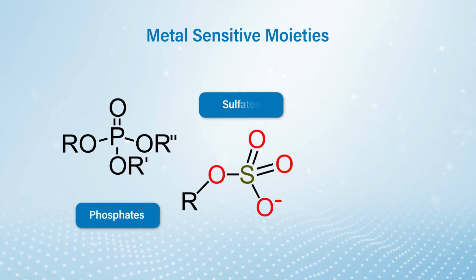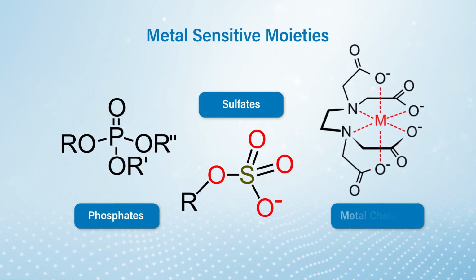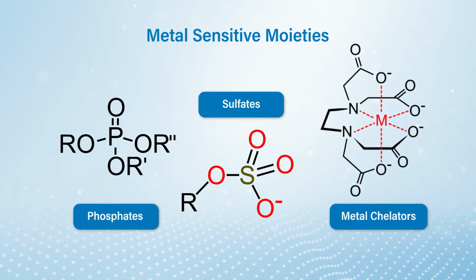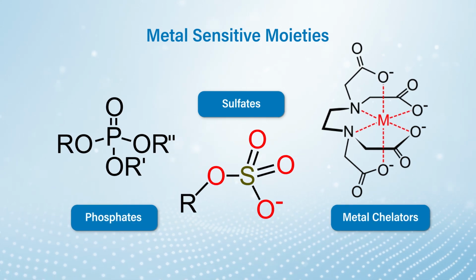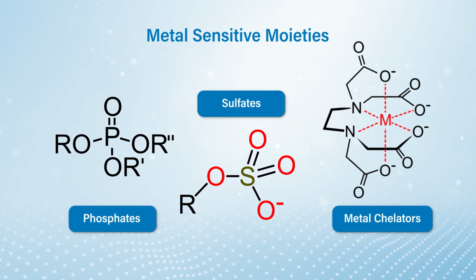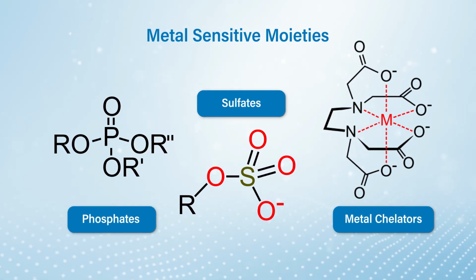Have you heard of that? Yeah, so you're exactly right. These phosphorylated or metal chelating groups, what can happen is they'll react ionically with the metal ions, whether it be the iron or the titanium ions in the hardware. And this can happen both on the LC column itself, as well as the actual LC system hardware, things like the needle and the flow path.